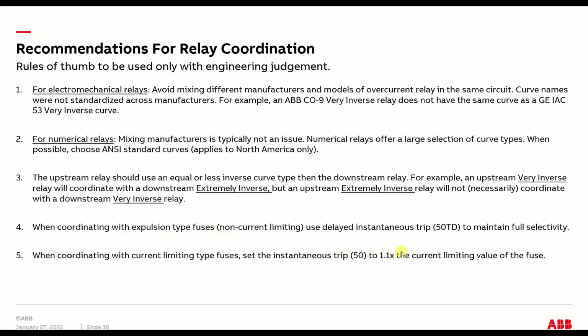Here's a couple little tips on coordinating with different types of fuses. If it's an expulsion fuse, you usually want to use a delayed instantaneous. If it's a current limiting fuse, you can use full instantaneous protection, no delay, and rule of thumb's about, you set that to about 110% of the current limiting value of the fuse. That gives you enough clearance time.